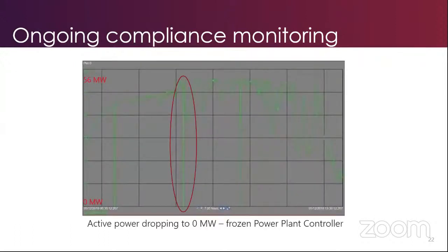Just to highlight the importance, this is from a solar farm in Queensland. Maximum capacity was about 56. You can see from the beginning it's starting up at the beginning of the plot and ramping up generation throughout the day, hitting the maximum around the middle of the plot. You can also see these spikes. It's dropping the power to 0 three times, which means while the system is operating, it is losing 56 megawatts of power all of a sudden, without anyone knowing what that is. And some other generator has to compensate for that, which is not ideal.